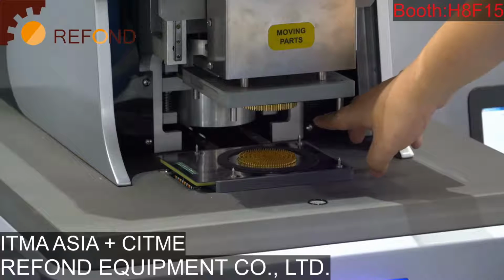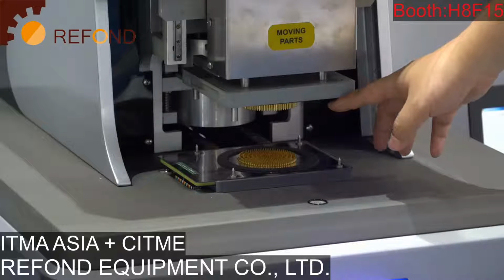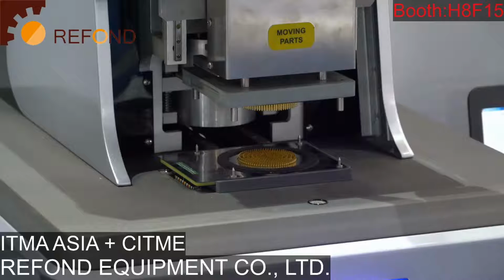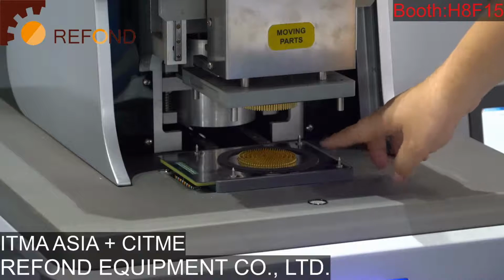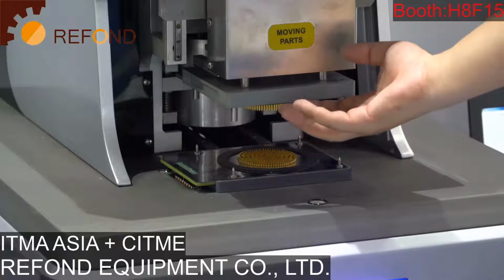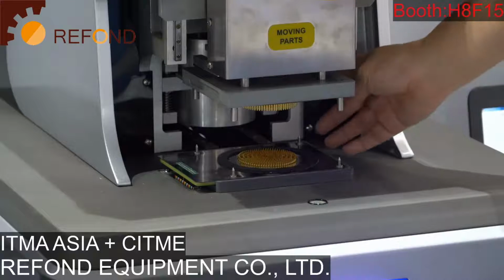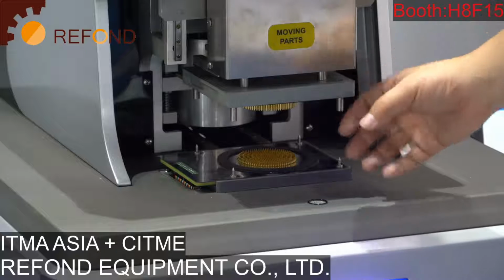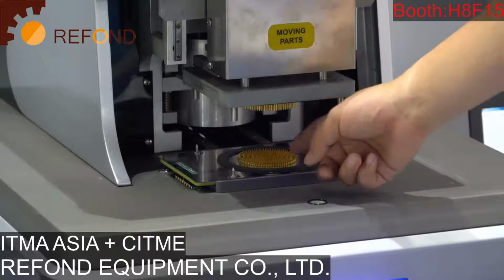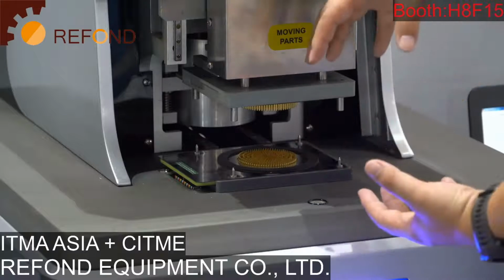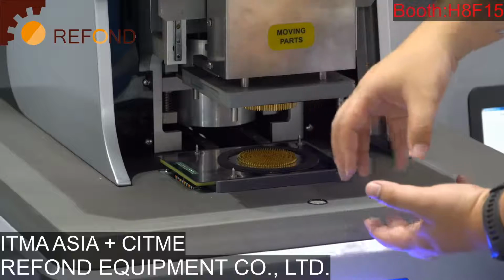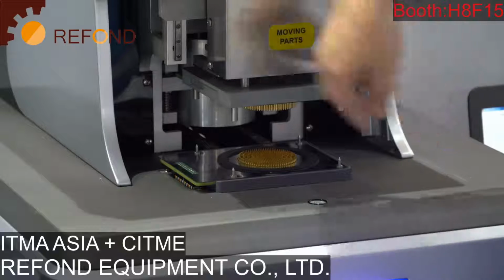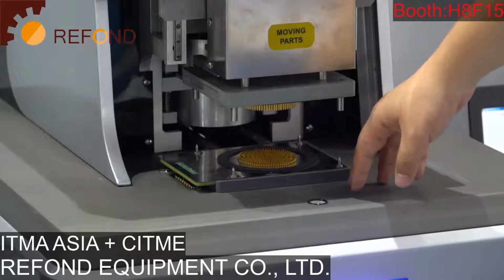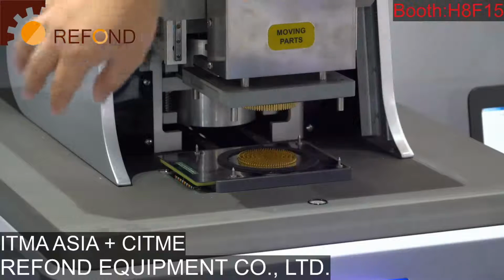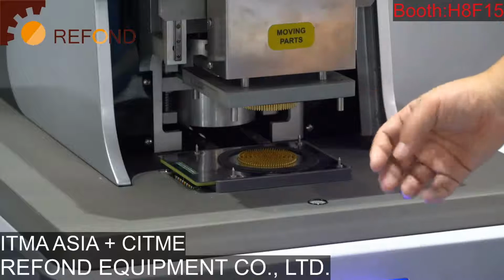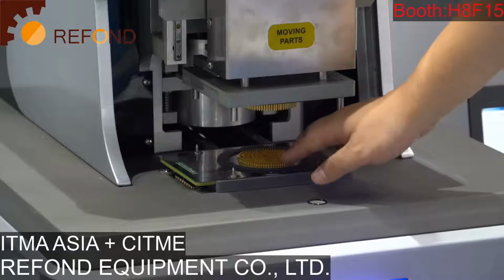In the back of the machine there is a cleaning cup. When you use the cleaning function, the top test head will move up, and then the cleaning cup will move forward and be placed in between the top and bottom test heads. The top test head will come down and seal the inside of the cleaning cup. Then clean water will be pumped from outside to clean all the pipeline and also the testing probes.